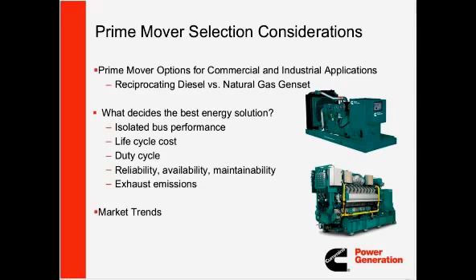The duty cycle is very important. Understanding whether it's going to go into a standby application, a prime application, or a continuous duty application will determine what fuel type you need for your application. When we talk about standby, it could be emergency standby, or it could be optional standby. When we say prime, we're talking mainly in situations where you don't have a reliable grid, where your generator is the prime source of power, or it could also apply to peak shaving applications and base loading type applications.